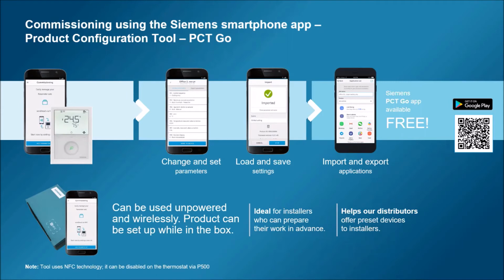And when you go on your site, you can plug them onto the mounting plate that you have wired properly, and then the device works. It can be useful if the KNX network is not running. It can be useful if you want to test the wiring. And this app is already available on our Google Store, and it comes for free. So it's on top of any other commissioning solution.